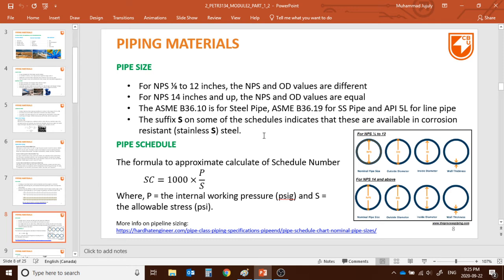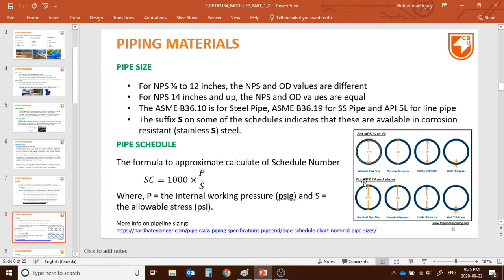For NPS 1/8 to 12 inch, the NPS is actually somewhere inside — nominal, between the OD and ID. But for NPS 14 or above, the outer diameter equals the NPS. Now that we know NPS tells us about the outer diameter, we need thickness information to fully define a pipeline. That's why we have the pipeline schedule number.